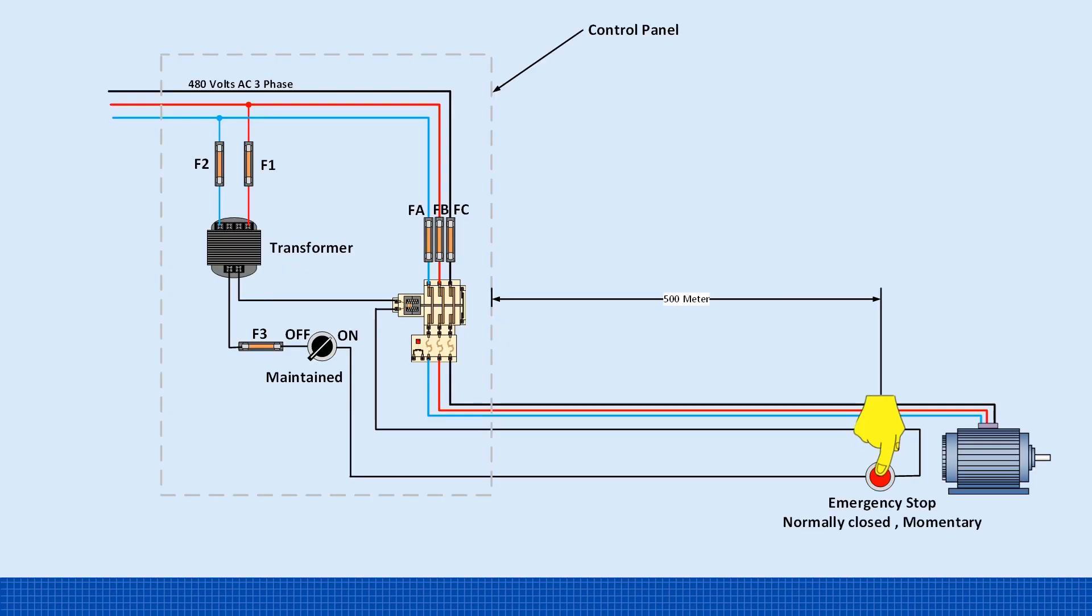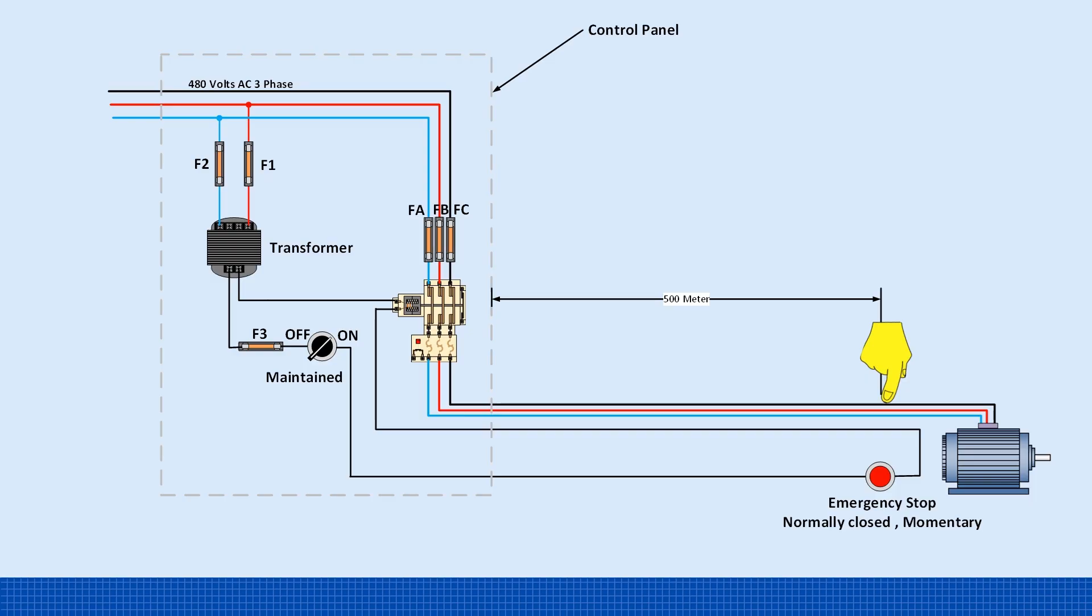In an industrial setting, this kind of circuit can be hazardous. Simply taking your hand off the emergency stop allows it to return to its normally closed state, and the machine re-energizes immediately without turning the selector switch back to on again. That means the system could restart unexpectedly, which is a serious safety concern. And often, the emergency stop is located hundreds of meters away from the control panel, so the operator might not even be near the machine when it powers back on. That's why we use latching circuits, to keep things off until a deliberate restart is triggered.